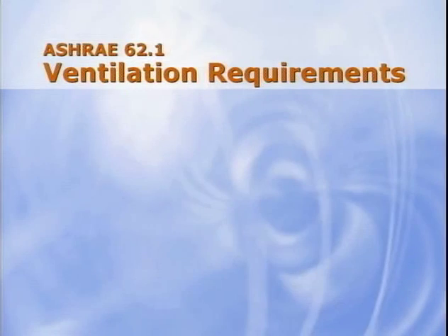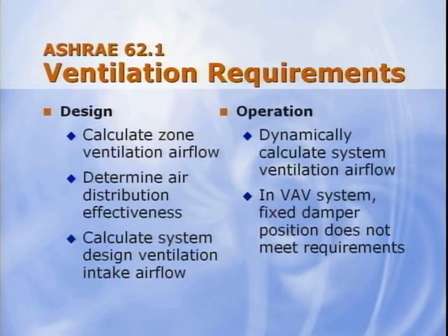Moving on to ASHRAE Standard 62, it requires that zone ventilation airflow be calculated, then corrected for the zone air distribution effectiveness, then calculated at the system level. During operation, to meet the standard's requirements, this system ventilation airflow can be dynamically calculated. Note that in a variable air volume system, setting the outdoor air damper to meet the design ventilation requirement, then leaving it at that position does not meet Standard 62 requirements. As the system airflow is reduced, bringing in the same amount of ventilation airflow requires the damper position to change, resulting in a larger percentage of outdoor air at off-design conditions.